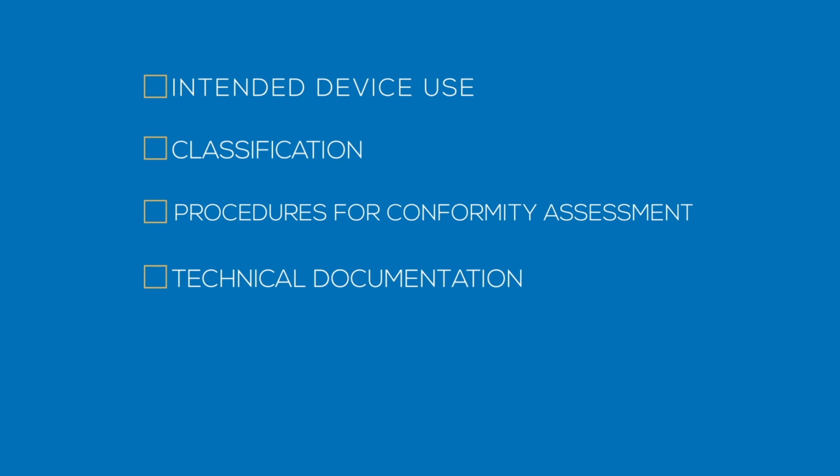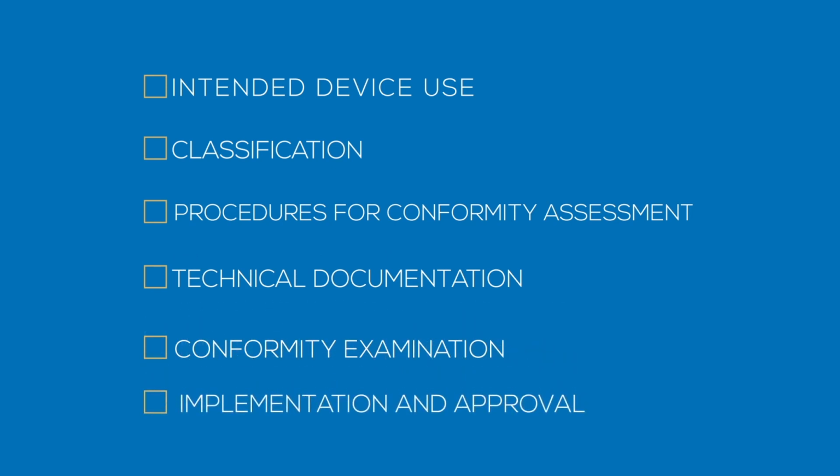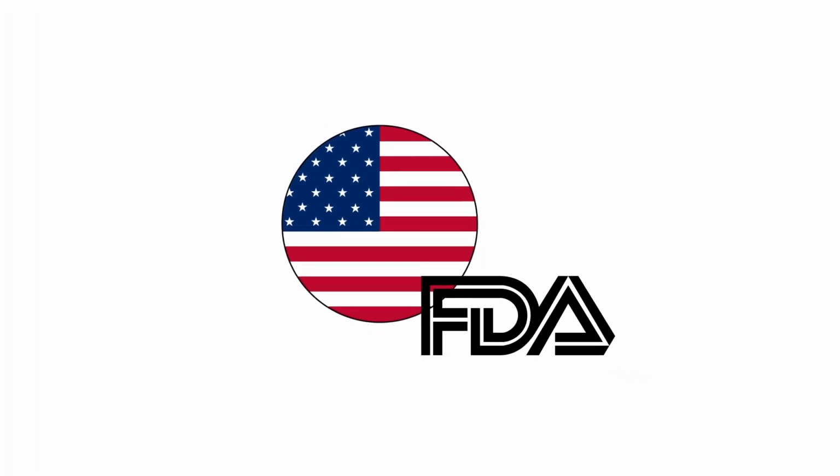Present the documentation for examination by the notified body and, where necessary, register the product with a national competent authority for medical devices. And finally, implement the conformity assessment procedures and receive the certificate of conformity in order to market the device with the CE mark. Medical device regulation in the US is the job of the Centre for Devices and Radiological Health, a centre within the Federal Food and Drug Administration.